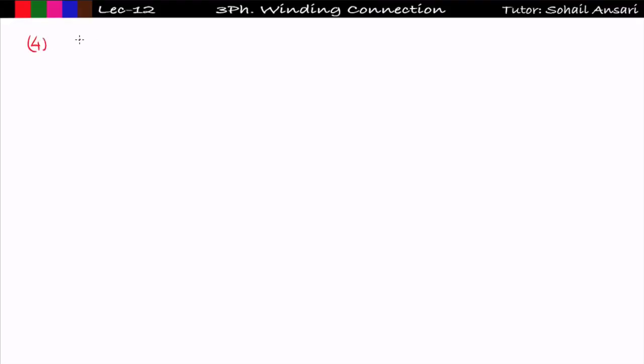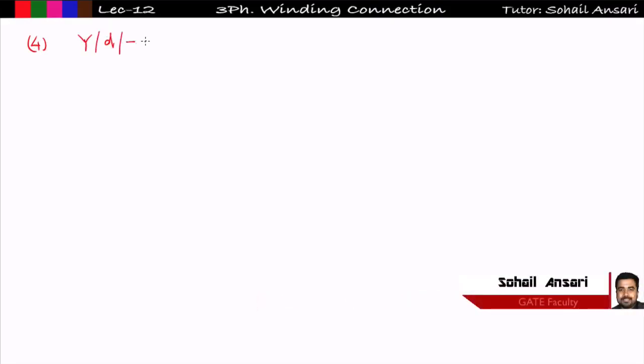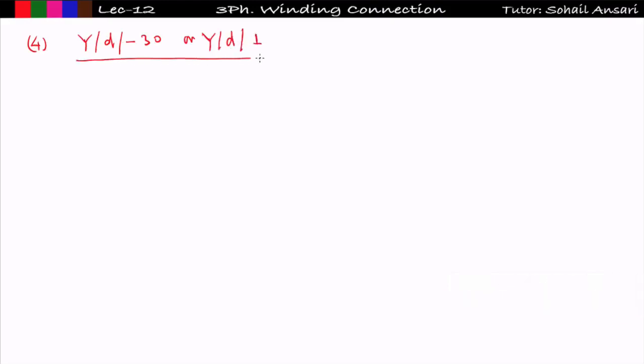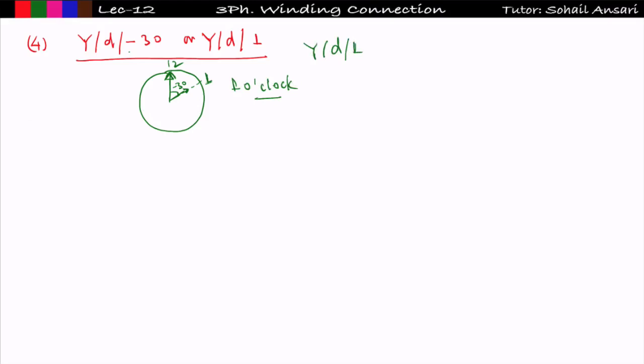The first point is how to make a YD-30, which can also be called YD1. In this winding connection, the primary is star connected and secondary is delta connected — that is a low voltage winding. The line-to-neutral voltage of the low voltage winding phasor is lagging behind by 30 degrees. In clock notation, at 12 the high voltage is fixed and the low voltage side lags by 30 degrees, making it one o'clock — that's why it is known as YD1.